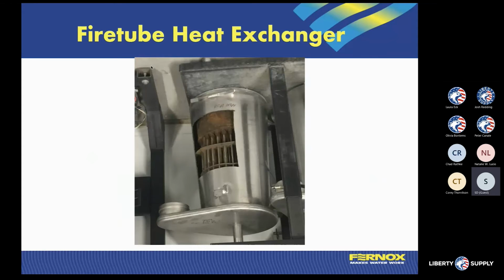So one of the counter effects that we've been talking about is heat exchangers. When we talk about water quality and displacement of failed components, usually it's going to start at the hottest point of the system. So in the case of a heating system, it's going to be your boiler heat exchanger. So there's a picture of a failed boiler heat exchanger after 18 months with a system that had bad water quality and the water was not treated. You can see from the burner side, the top of that unit, and from that down, we're starting to see the buildup of the scale, the hardness, and in this case, iron oxide, which is the byproduct of black iron or steel piping systems.